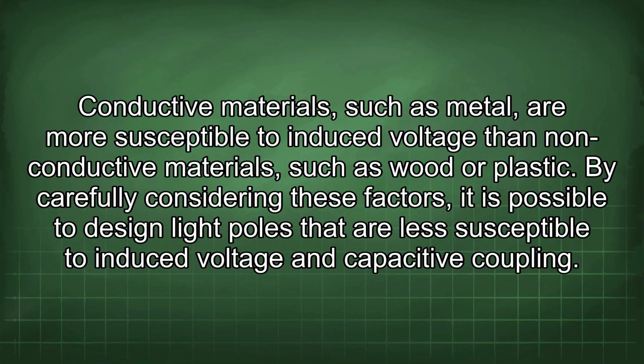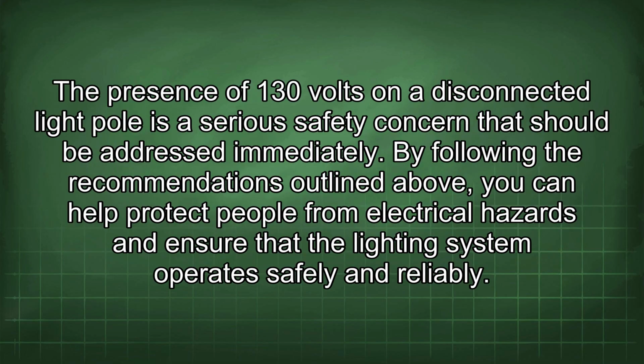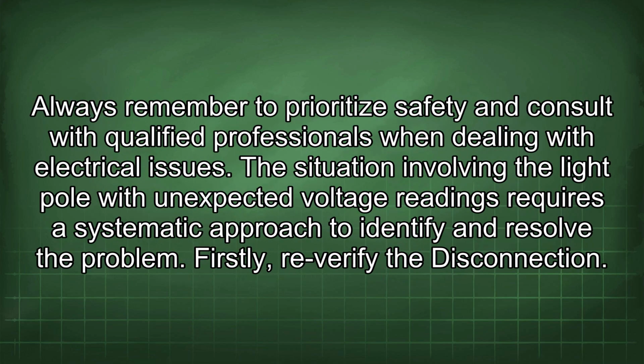By carefully considering these factors, it is possible to design light poles that are less susceptible to induced voltage and capacitive coupling. The presence of 130 volts on a disconnected light pole is a serious safety concern that should be addressed immediately. By following the recommendations outlined above, you can help protect people from electrical hazards and ensure that the lighting system operates safely and reliably. Always remember to prioritize safety and consult with qualified professionals when dealing with electrical issues.